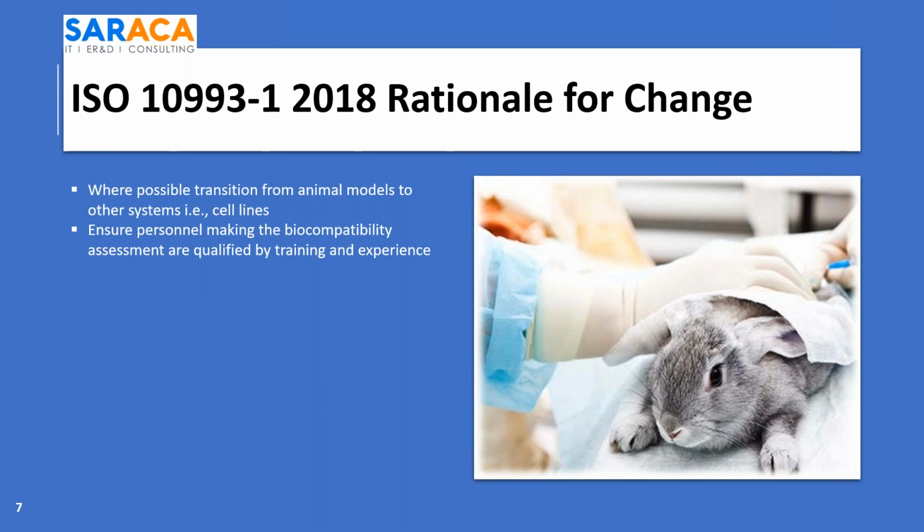The next point that I would like to ensure that everybody understands is this: ensure personnel making the biocompatibility assessment are qualified by training and experience. Prior to this implementation, anybody that worked in the laboratory was considered, or had experience, was considered adequate training. Now they want you to be thoroughly trained, thoroughly documented as being trained, and have the experience to make biocompatibility decisions for a device.